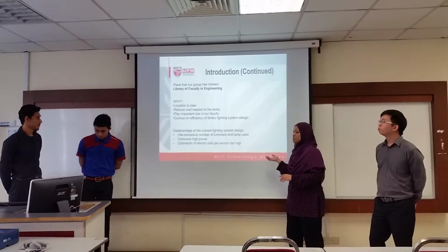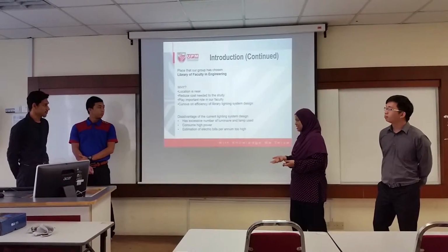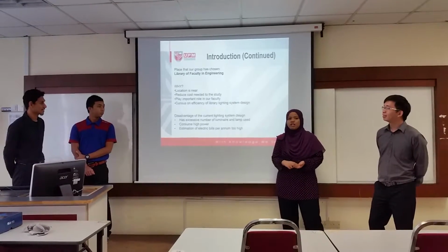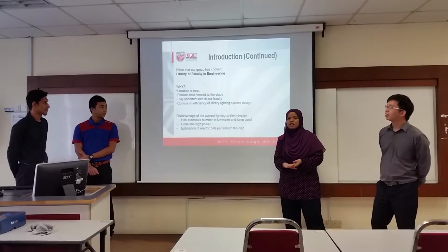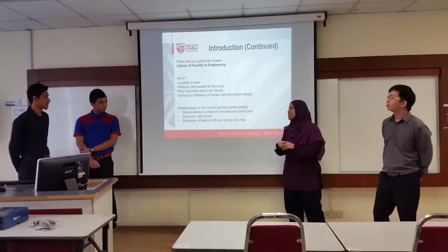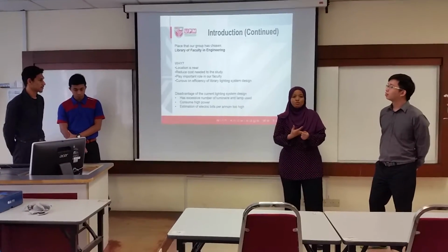The disadvantages of the current lighting system design are, first, the excessive number of luminaires and lamps used. The second is that it consumes very high power while producing very little lux. And the last is that the estimated electric bill per annum is too high.